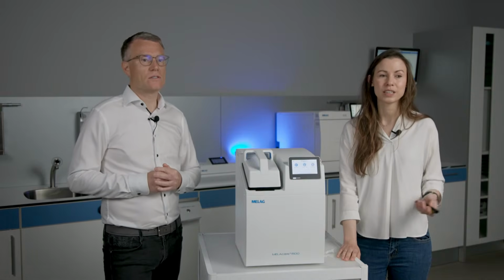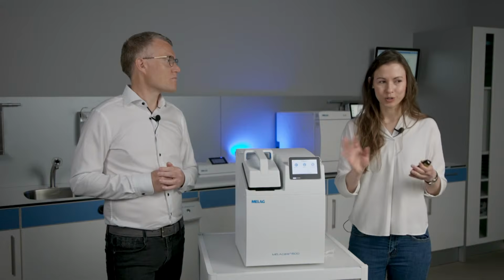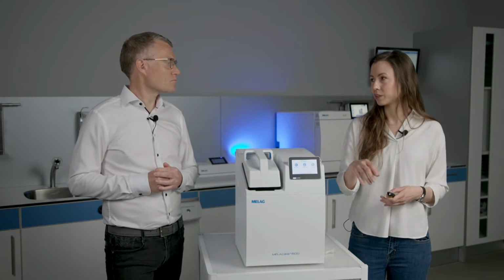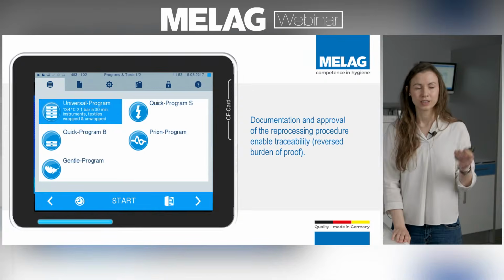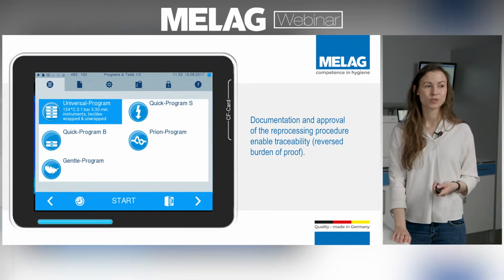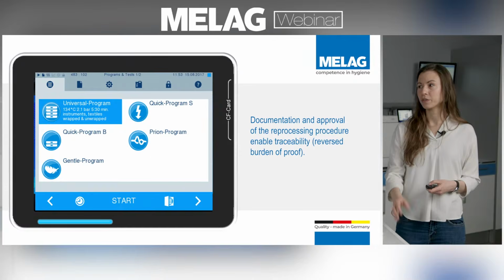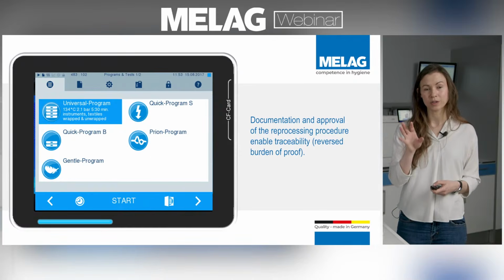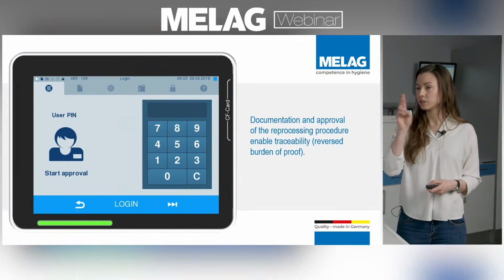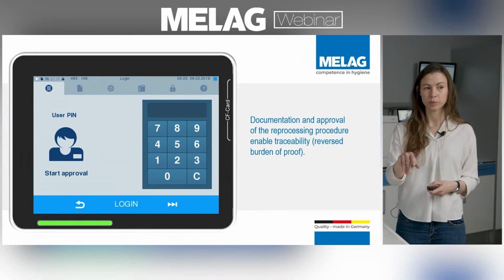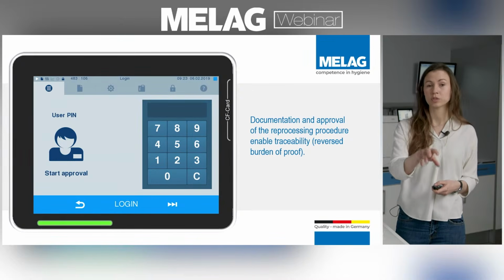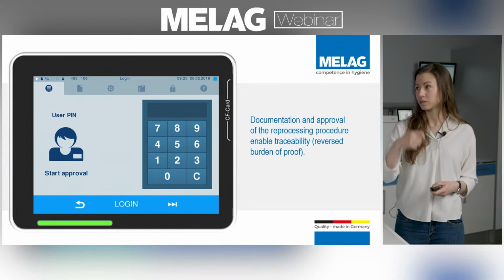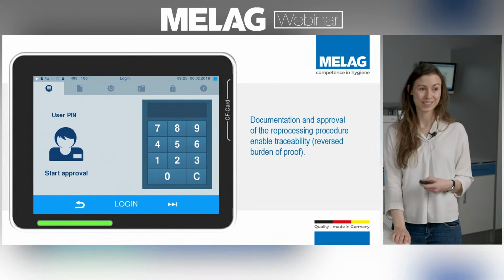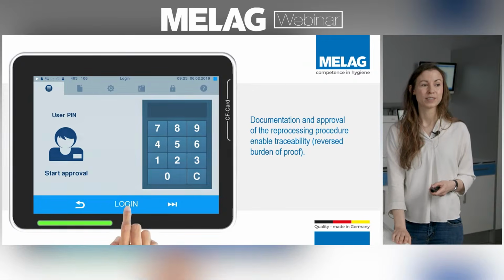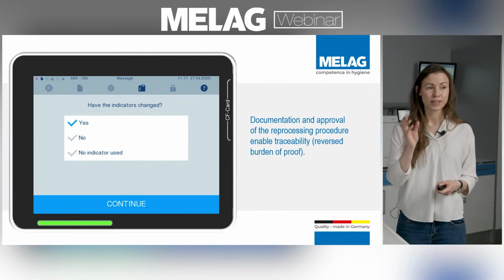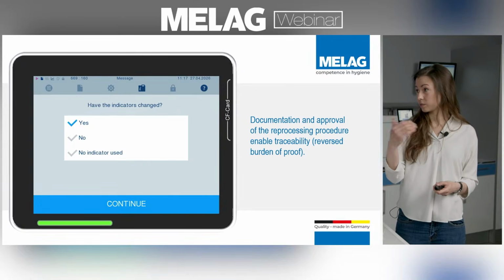So how does it look? Maybe let's just go through the cycle really quick to show you how easy it actually is. Like Leonard already mentioned, you first choose your program. Then when the device has a user authentication, you can set up that the user has to enter a 4-digit PIN, which will be documented in the protocol as well as on the label that is stuck onto the instruments after it is sterilized. And then you have to say, for example, did the indicator change? Like the helix test, for example?